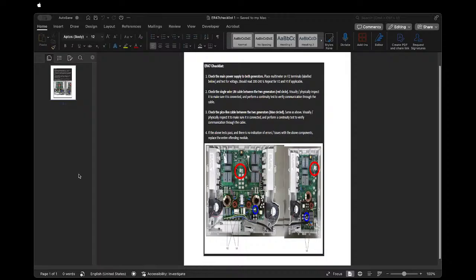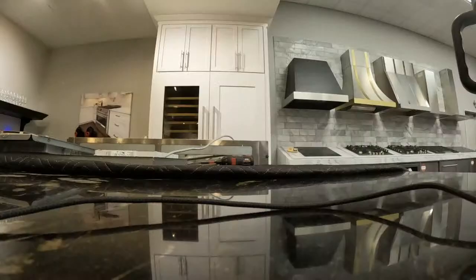So if we can confirm voltage, and confirm that our wires and bus connectors are plugged in correctly and that they actually have continuity, you can always take it a step further. Pull your multimeter out, check from end to end, and make sure they are reading signal. It's a rarity, but it does happen in the field sometimes. At this point I'm going to take that off the screen, and I'm going to have Shiloh grab the GoPro, and we're going to get a little bit closer on this 48-inch induction module here.